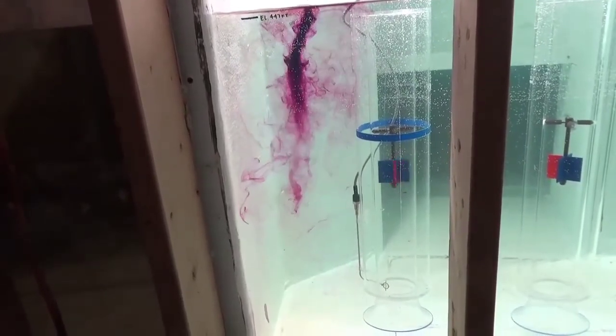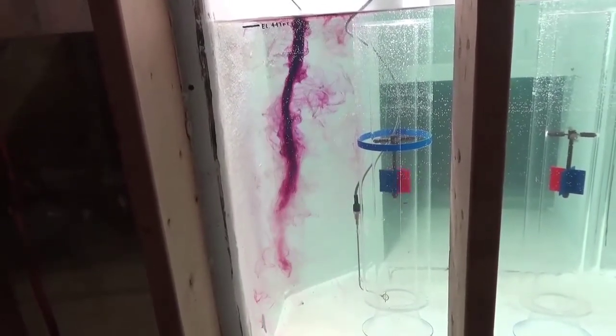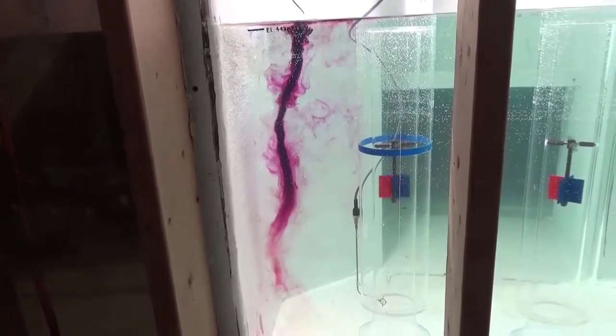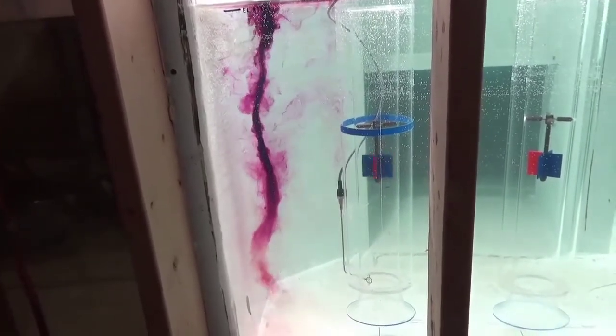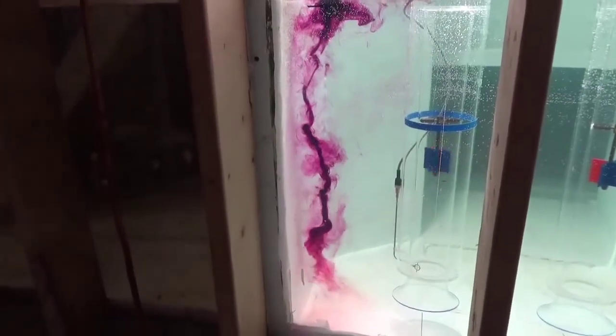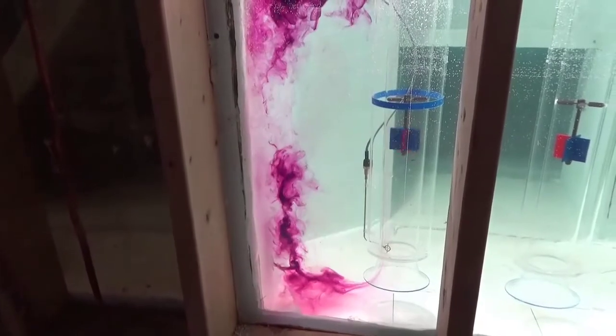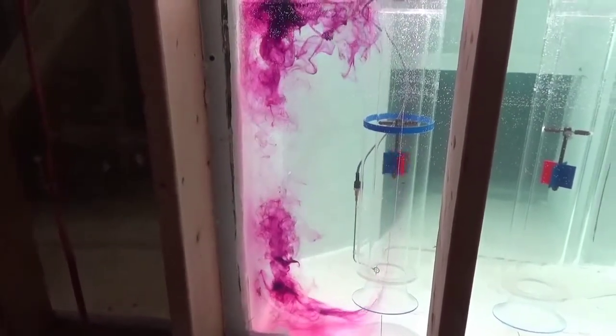Again, they're forming. They're not a very high velocity core, but they are organized. You can see it going down here. It's working its way in. And it will get all the way to the pump, and it may break itself up. You can see it starting to, that ribbon will get itself down into there. This one here is going to decide to break up a little bit. They're not the big problem. The big problem here is the pre-swirl.